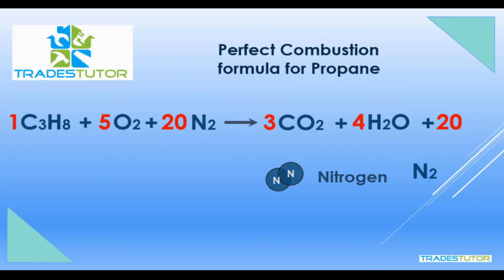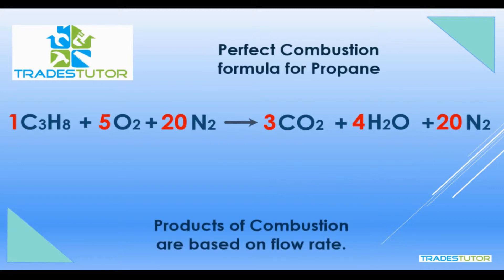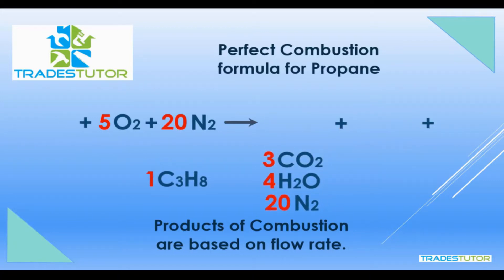So there's your formula. When we find the products of combustion, this is going to be based on flow rate, and that flow rate can be in cubic feet or cubic meters — for our purposes we'll deal with cubic feet. What we want to find out is: if we send a certain amount of propane in, how much of the products of combustion do we get on the other side? That relies on the ratio. For one C3H8 — one propane — you get three carbon dioxides, four water vapors, and 20 nitrogens. That's how you calculate what you get out the other side based on what you put in. We're always based on one, but we're going to have more than one cubic foot of flow rate, so we'll need to calculate that.